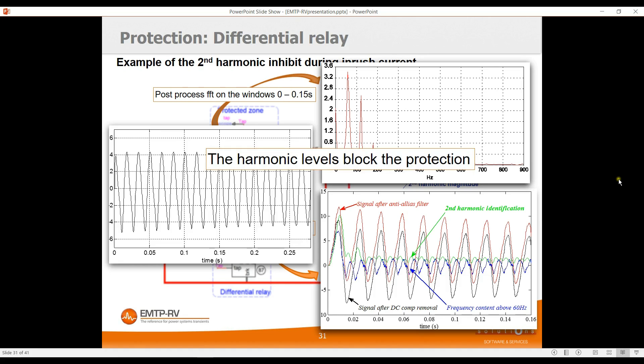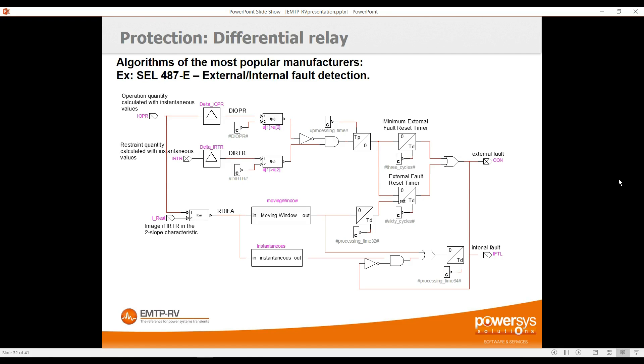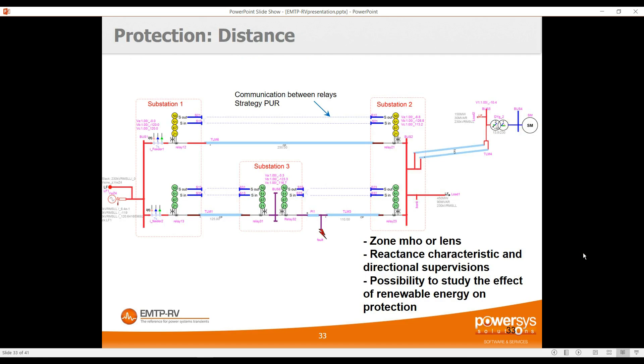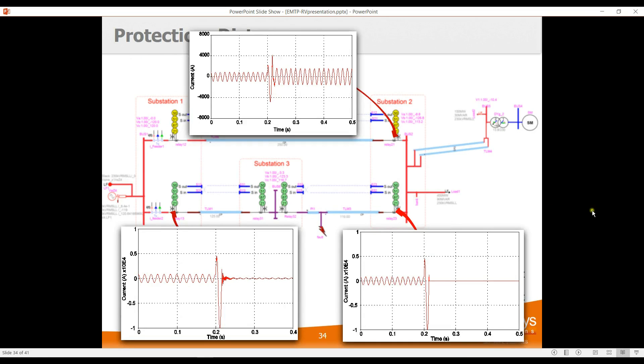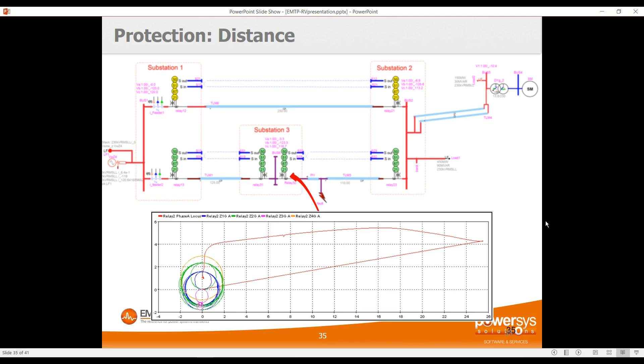Manufacturer relay algorithms can be used — for example, a Schweitzer relay model. Distance protection can also be studied, including modeling the communication between relays and different voltage polarization algorithms from manufacturers. In this example, a fault occurs in zone one of one relay and zone two of another; they communicate and both open instantaneously at the first zero crossing of the current. One interesting feature is displaying the impedance locus on an R-X graph, showing the expansion of zones when the fault occurs — zone one, two, three — and how the reverse zone changes.